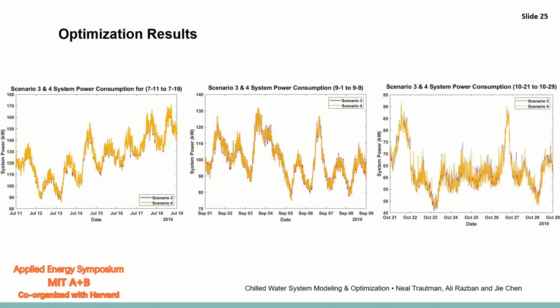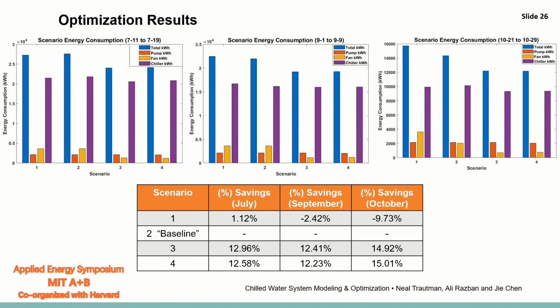And finally, these graphs compare scenario 3 and 4. As you can see, there's practically no difference between the two, which would indicate that there is almost no advantage to optimizing the condenser water pump with a VFD. This would indicate that almost all the savings that can be achieved through optimization of both the condenser water pump and the cooling tower fan can be achieved through optimization of the condenser water cooling tower fan by itself.